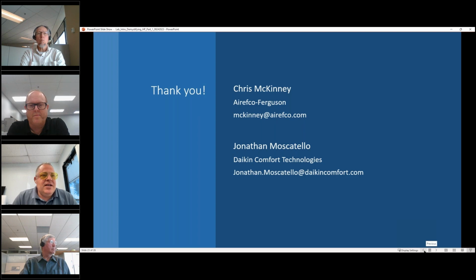And Chris and I can attest from our experience in our own homes and in the field that appears to be true. From a mechanics standpoint, we remember that cruise control concept that we communicated and the part load efficiencies that result. When a heat pump is asked to recover more than this 3 degrees setback for comfort, the machine has to work harder and operate more at its fullest capacity to try to return that space. The machines are less efficient when they're operating at their full capacity. They use more power, but the energy efficiency of that power goes down as well. And so that's a contributing factor to why setbacks are undesirable.